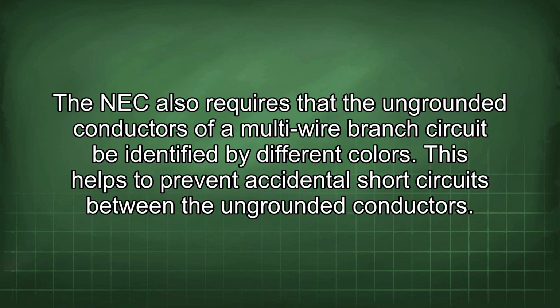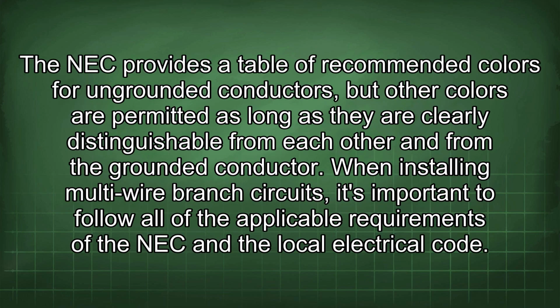The NEC also requires that the ungrounded conductors of a multi-wire branch circuit be identified by different colors. This helps to prevent accidental short circuits between the ungrounded conductors. The NEC provides a table of recommended colors for ungrounded conductors, but other colors are permitted as long as they are clearly distinguishable from each other and from the grounded conductor.